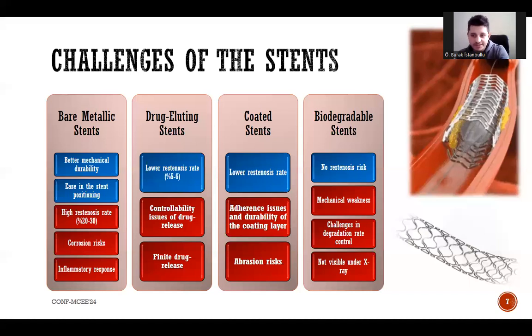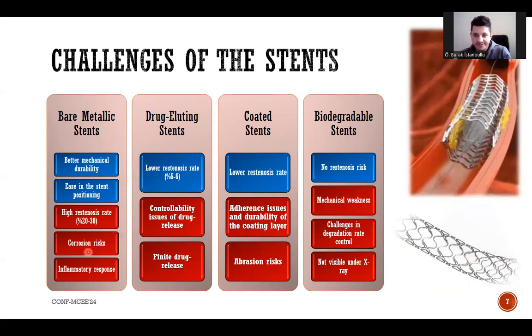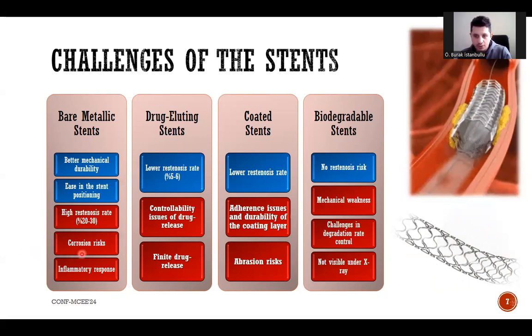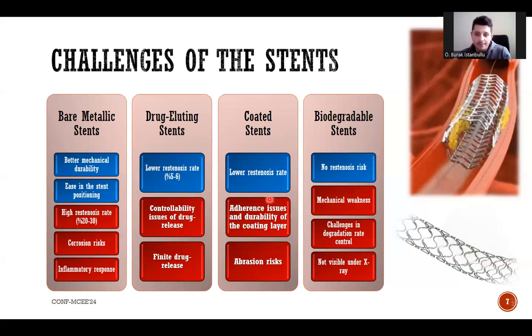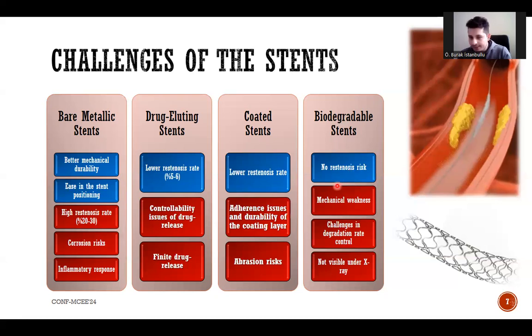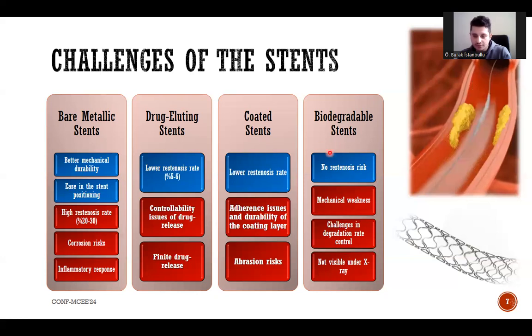Comparing the four main stent groups, the first three groups can provide better mechanical features and stent positioning and deployment compared to biodegradable stents. However, the higher restenosis risks, corrosion issues, controlling the drug eluting mechanism for drug eluting stents, and the abrasion risks of the coating layer for coated stents are main challenges of these three groups. Despite there being no restenosis risks in biodegradable stents, their mechanical weakness, degradation rate control, and accurate positioning within the vessel are the main challenges that need to be addressed.